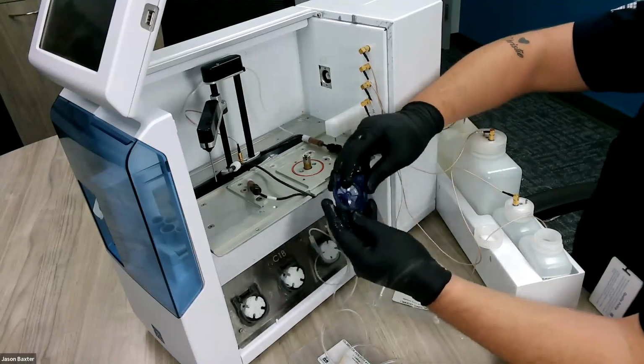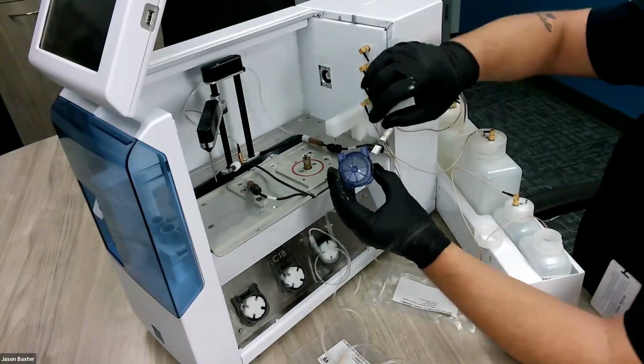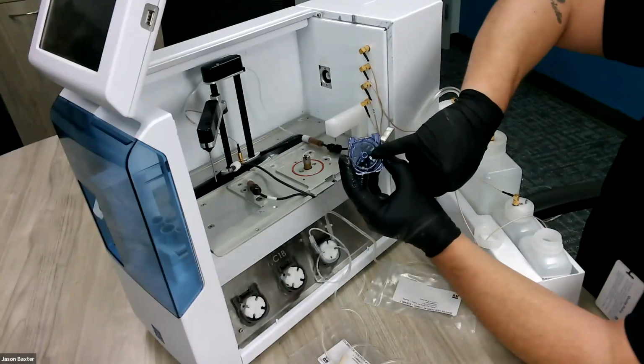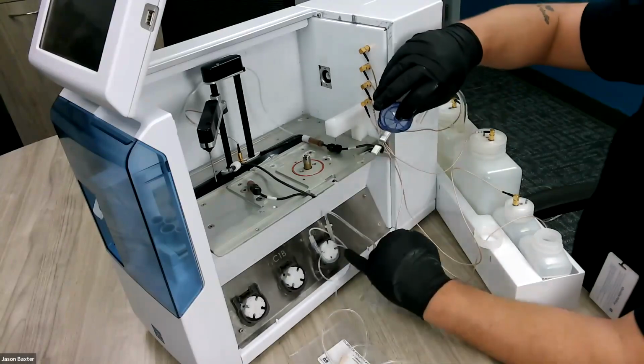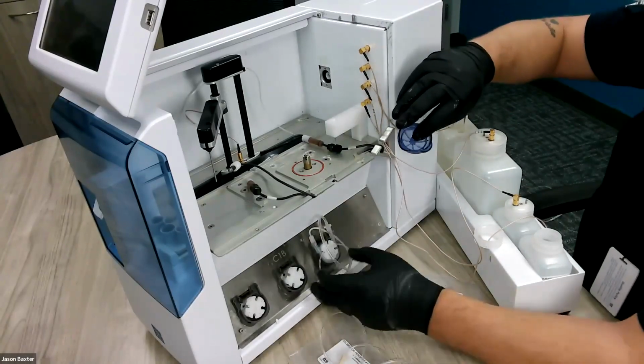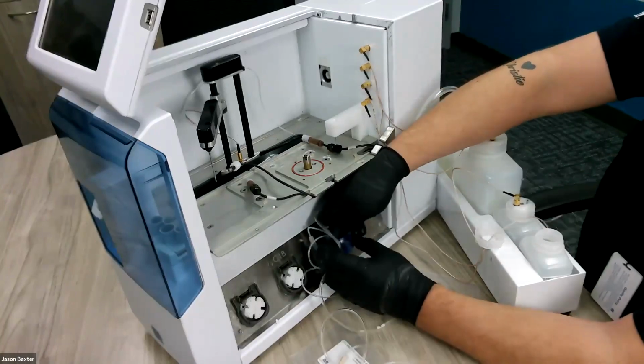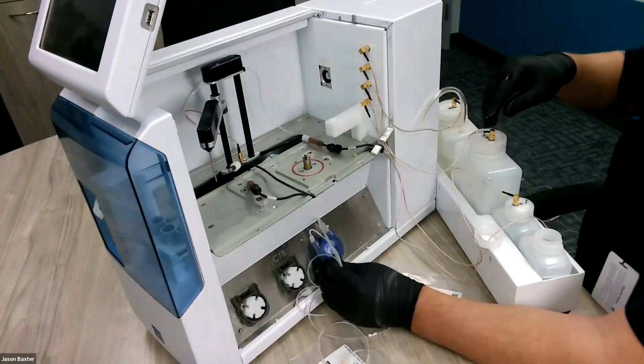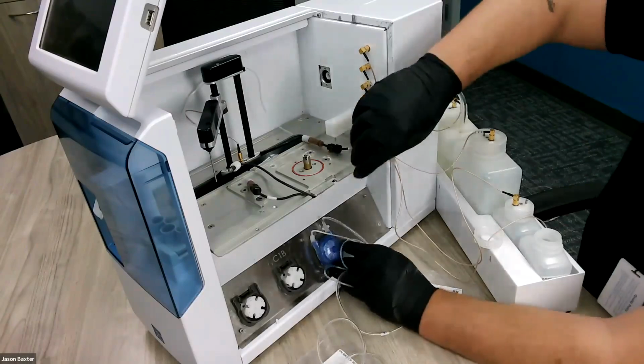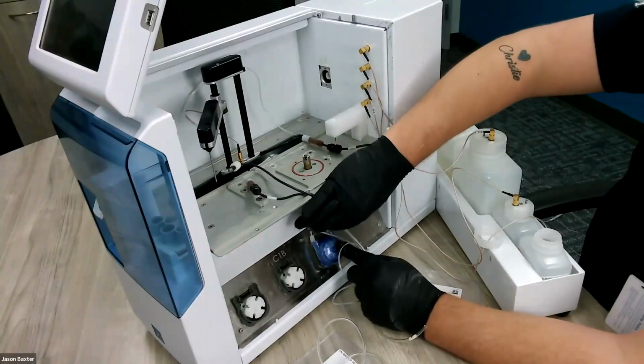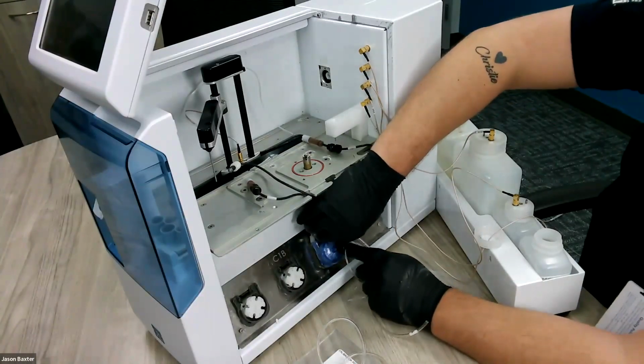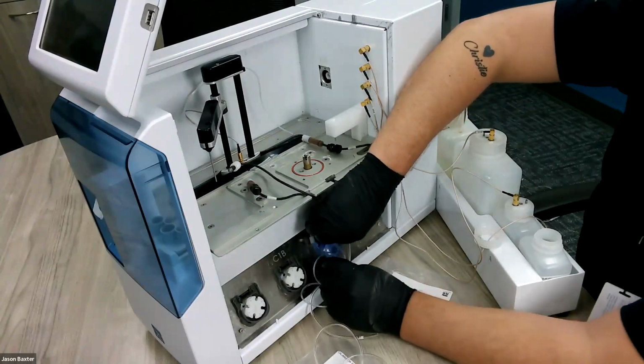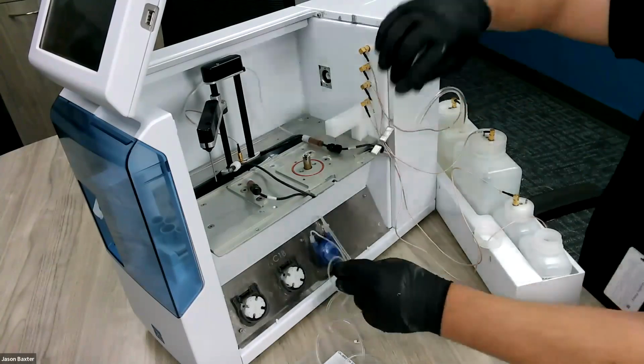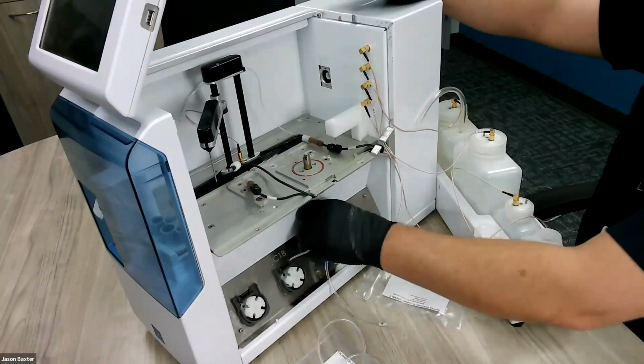before installation. When I install these, you'll notice the inside of the cap has a small hole in the center of it, and you'll notice the peristaltic pump wheel has a post that sticks out. All you have to do is line up the cover on top of the post, and then I will gently grab a hold of the square fitting on the buffer pump and lift it upward, and that will give me clearance to install my buffer cap.